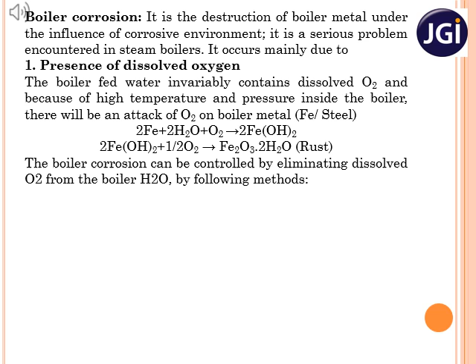Hence, by eliminating dissolved oxygen from the boiler water by one of the following methods, boiler corrosion can be controlled. First one, by adding oxygen scavengers to boiler water. This method is called chemical treatment. Normally, the scavengers will be a reducing agent which can react with dissolved oxygen. Example, hydrazine. This hydrazine reacts with dissolved oxygen to form water and nitrogen gas. Another one is a mechanical method wherein water is passed through the deaerator made up of perforated plates. The hot water is passed through these plates and released oxygen is sucked by using a vacuum pump.